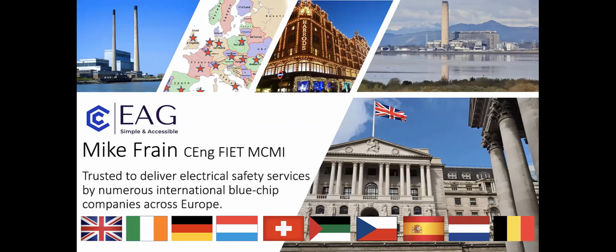But the first question that we've got come in here is from Paul, and he's requested, as much as the arc flash research and the IEEE standard is based on US switchgear and practices, how does this directly correlate to the different construction of switchgear in the IEC world and the different more stringent standards, such as not just the IEC, BS EN standards, but the LVD, which requires safe design, which should fundamentally minimize the risk of arc flash by law, not just by product standard, which should reduce the risk lower than the minimum legal requirements.